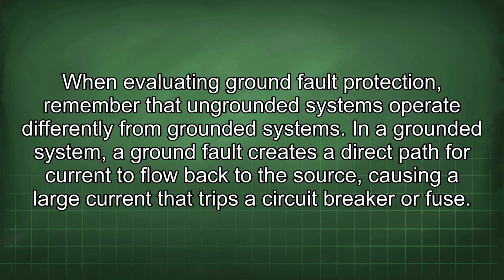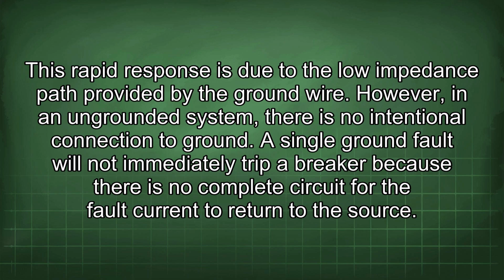When evaluating ground fault protection, remember that ungrounded systems operate differently from grounded systems. In a grounded system, a ground fault creates a direct path for current to flow back to the source, causing a large current that trips a circuit breaker or fuse. This rapid response is due to the low impedance path provided by the ground wire. However, in an ungrounded system, there is no intentional connection to ground. A single ground fault will not immediately trip a breaker because there is no complete circuit for the fault current to return to the source.